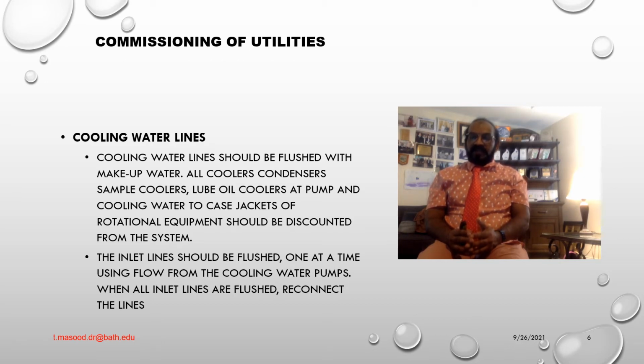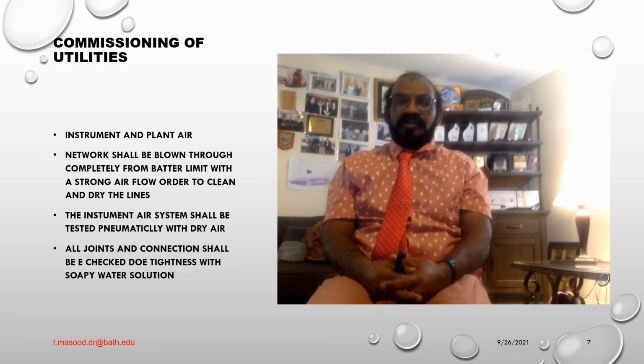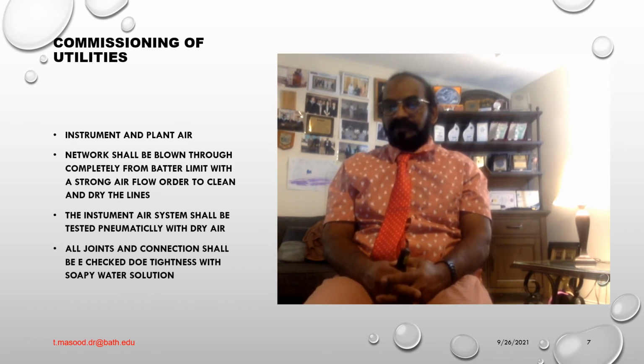One at a time or using a flow from the cooling water pumps. When all inlet lines are flushed, reconnect the lines, disconnect the cooling water outlet lines from the users, flush through the user, then reconnect the outer lines. When all outer lines are connected, flush the return lines. Okay, commissioning of utilities. Next topic, instrument and plant air system.